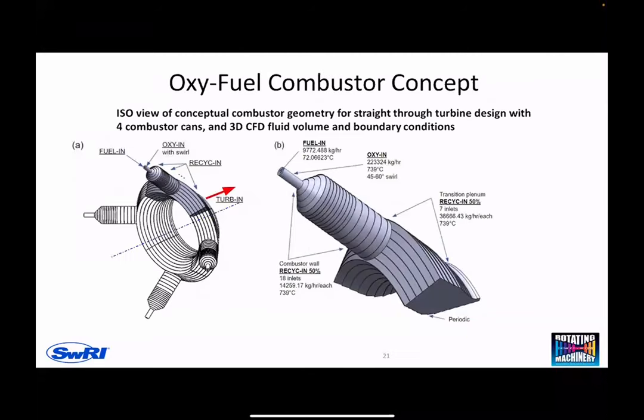Part of the program was also looking at what the combustor looks like. So what we're seeing here is an example of our straight-through turbine combustor cans coming in at a 45 degree angle into a collector plenum or transition piece. We also looked at what fuel is required in the combustor, and the temperature profile coming out of it - what we're really looking for is uniform temperature going into the turbine flow path.